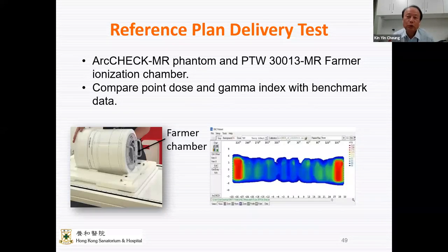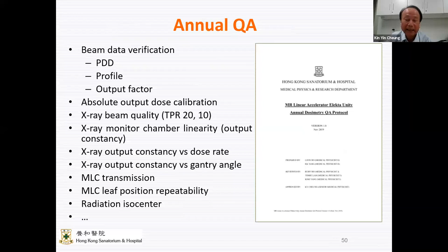And we also do a reference arc check plan delivery, a complex treatment plan, and check the consistency compared with the benchmark data to ensure the beam delivery and the dosimetry are in order. And then annually, over the year, we do an annual check.